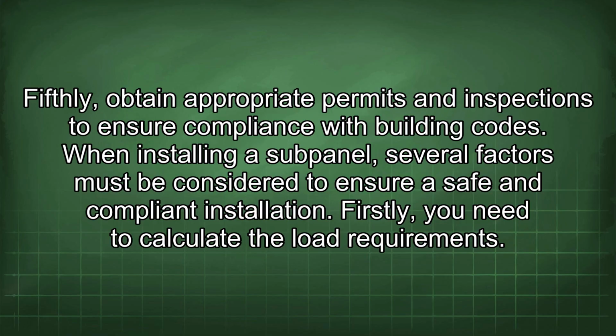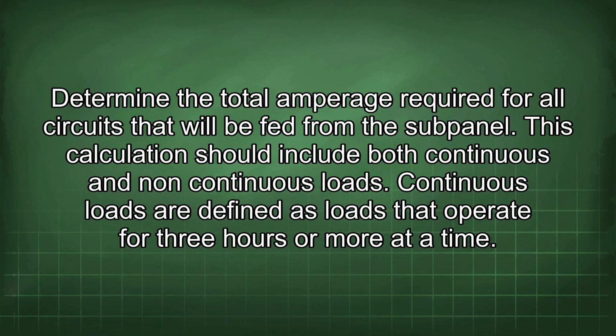When installing a subpanel, several factors must be considered to ensure a safe and compliant installation. Firstly, you need to calculate the load requirement. Determine the total amperage required for all circuits that will be fed from the subpanel. This calculation should include both continuous and non-continuous loads. Continuous loads are defined as loads that operate for 3 hours or more at a time.